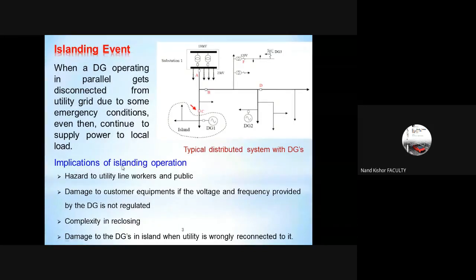Because of this islanding event, which could be intentional or unintentional, it could be hazardous to the workers who are working on the line somewhere, or to the public, or it may also damage some equipment if the voltage and the frequency are not being regulated by the utilities. Then complexity may arise in the reclosing operation of the DG, and in some cases damage to the DGs in islanding may occur if it is wrongly reconnected. We call that out of phase recloser operation. So these are some of the implications we are likely to have because of an islanding event.